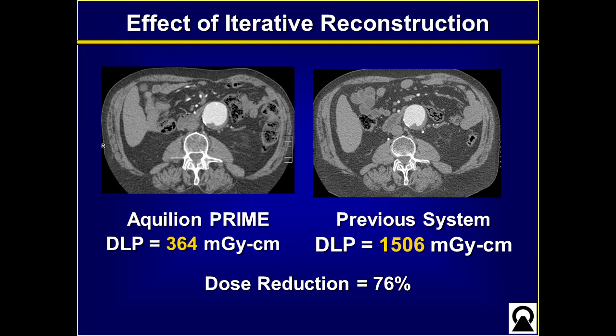You can see the benefits of these choices quite easily. Here's a patient with an infrarenal abdominal aortic aneurysm. On our new scanner, the DLP was 364. On our old scanner, same patient, the DLP was 1506 — more than a 75% reduction in dose. And if you look at the image quality, it's comparable, or if anything a little bit better looking at the paraspinal muscles on our new scanner at the much lower dose. This kind of decision is easy to make.